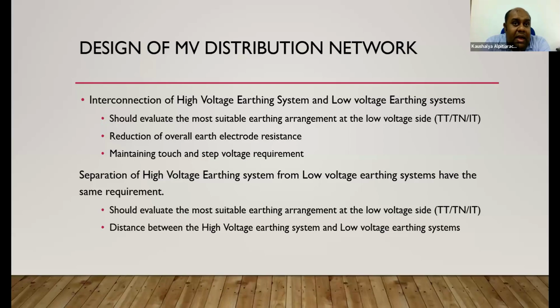Yes, reducing your earth electrode resistance to facilitate grounding of the fault quickly, and maintaining touch and step voltage requirements. In BS 7671, you have a cross reference for a few other standards regarding this. This is of course with the BS 7671. You can refer to Chapter 44 for the particular detailed jargon.